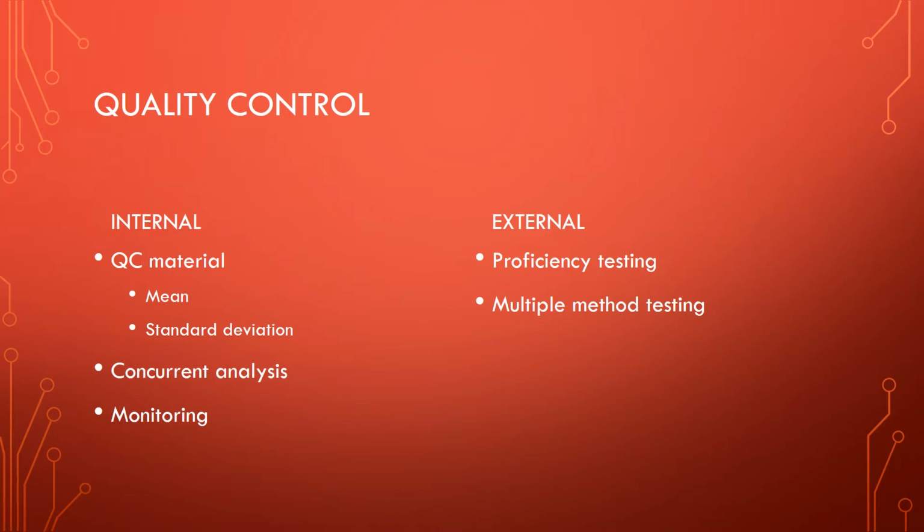Now, the CAP knows what the results are, right? They performed the tests as well. So CAP, whoever provides proficiency material, will know what the results should be, but we'll also compare the results that you get to every other institution that runs that analyzer or that procedure. And that allows you to compare how your instruments run.